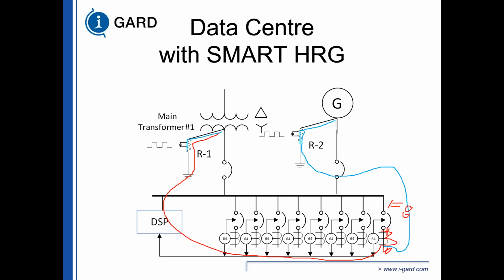Start looking here. You've eliminated 7 feeders where your incident energy is going to be the highest. And the maintenance personnel could start looking from here, and this can go to an MCC. Once you turn on the pulsing, it doesn't matter where that fault is, you're going to locate it. Not everywhere, sorry. You're only going to find the pulsing in the faulted path. So if you see the signature, you're in the faulted path, keep going downstream. You're only looking at one location to determine where the fault is.